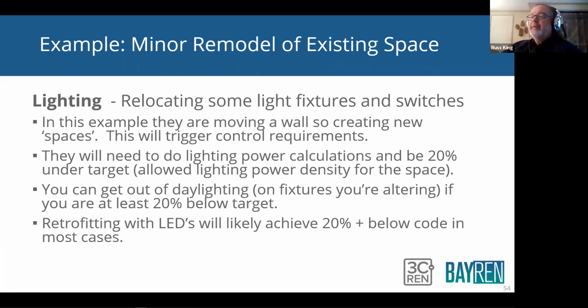So they're going to build out a wall to make an office. Now that office is going to have a light fixture in it. It has to have its own switch. When you walk into that office, you have to be able to turn that lighting off in that office independent of the rest of the building. They will need to do a lighting power calculation and be 20% under target, okay? If you can get out of daylighting by being less than 20%, all right?